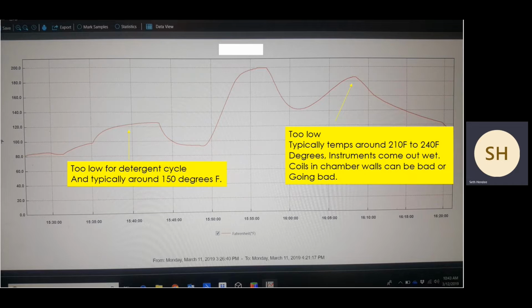So that's where the detergent cycle was, and we wanted it at 150, and that was too low. Then we get over to the final side here, and this dry is too low. Typical temps are around 210 to 240 degrees. So the instruments in this cycle came out very wet. Now, instruments may not come out bone dry, but these came out very, very wet. Everything was dripping, soaking wet everywhere.